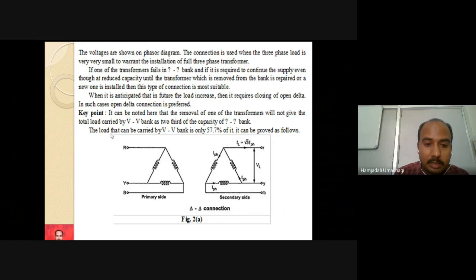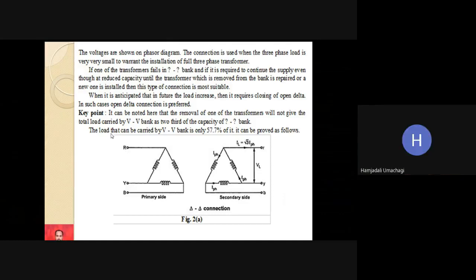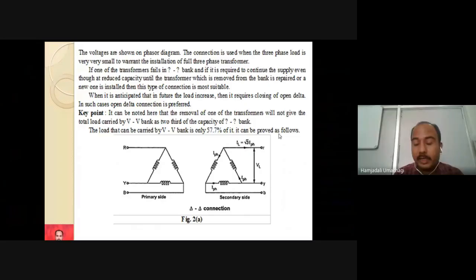The load carried safely can be proved as follows. Suppose this is my delta connection, and due to some failure one of the transformers goes out of service. Then it becomes open delta, this will be opened and this will be opened. In that case, how much safe load can it carry? The load carried safely by the VV connection is 57.7% of the earlier load. Suppose in the delta connection you have connected 100% load, then once it becomes VV connection, you should connect only 57.7% of the load. It means it can carry safely 57.7% of the loading condition, and this can be seen with the help of some derivation here.